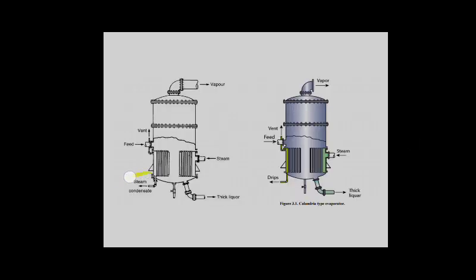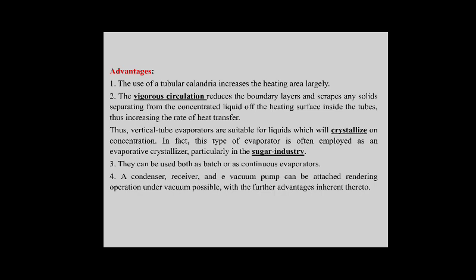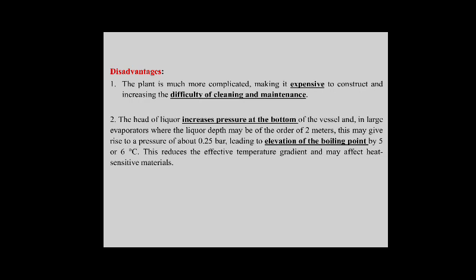The short tube (vertical tube) evaporator uses a tubular calandria which increases the heating area largely. Vigorous circulation reduces the boundary layer and scrapes any solids separating from the concentrated liquid. Thus vertical tube evaporators are suitable for liquids that will crystallize on concentration and are used in the sugar industry. They can be used as batch or continuous evaporators and may be fitted with a condenser, receiver, and vacuum pump. Disadvantages: the plant is much more complicated, making it expensive and difficult to clean and maintain. The hydrostatic head of liquor increases pressure at the bottom, causing elevation of boiling point, which may lead to serious problems.